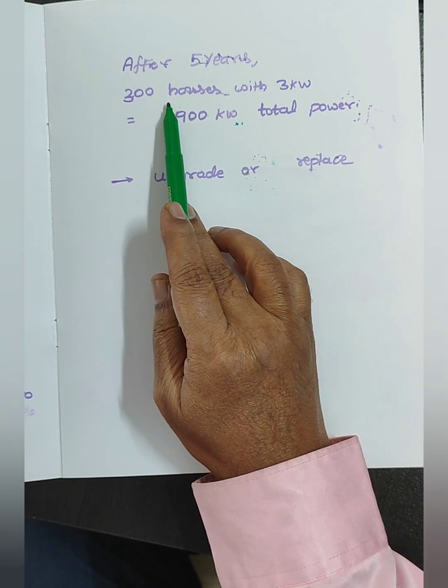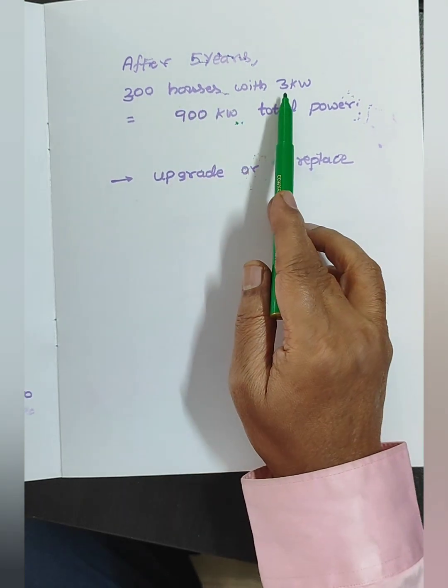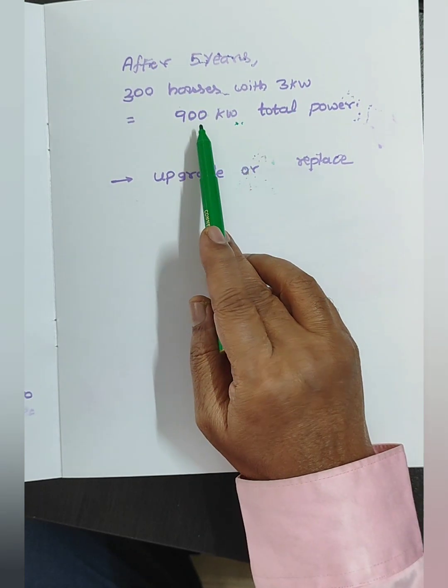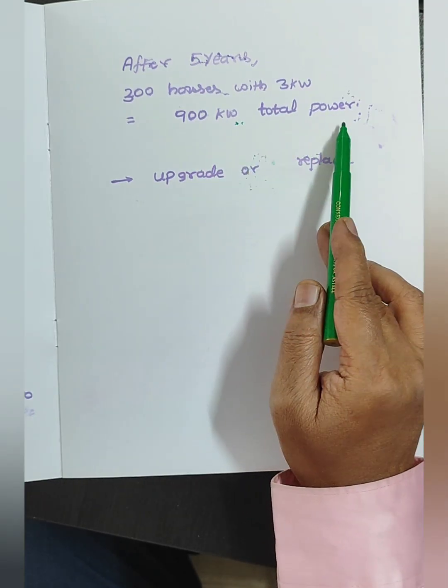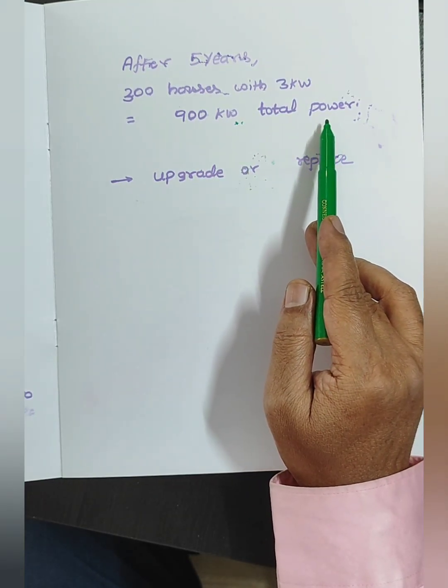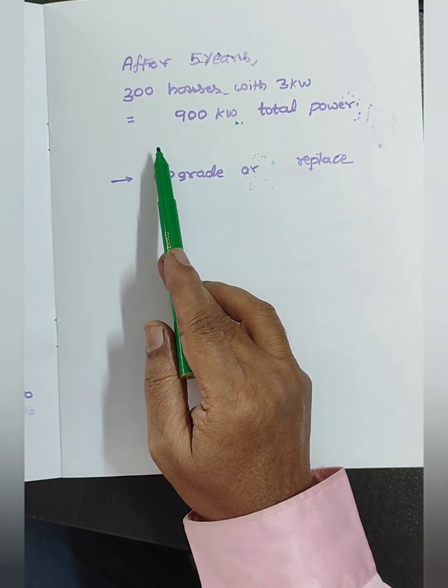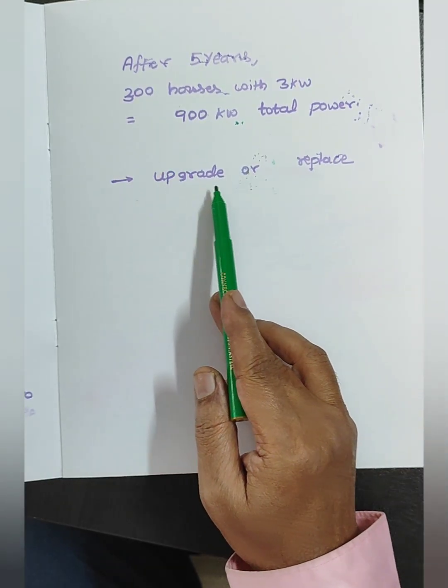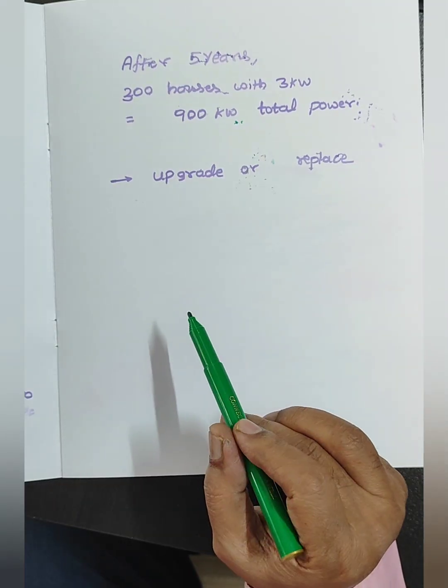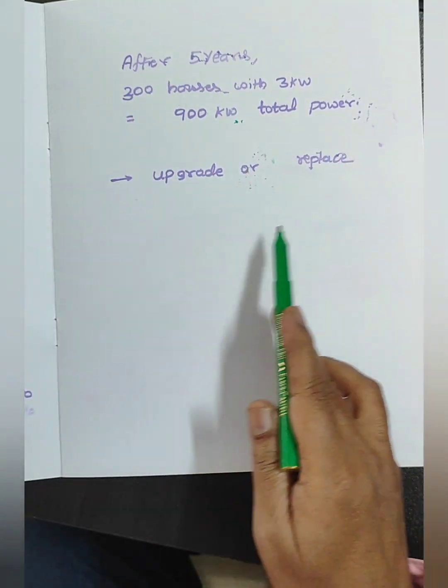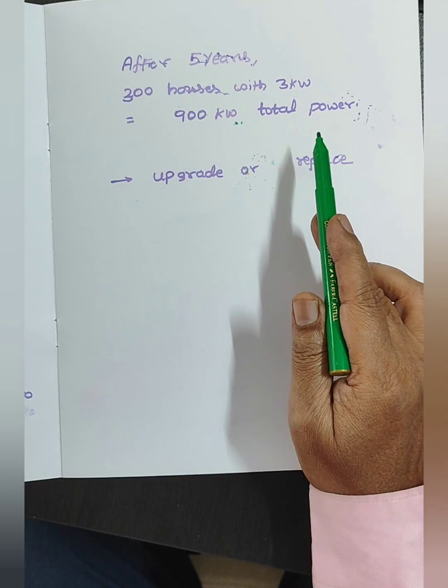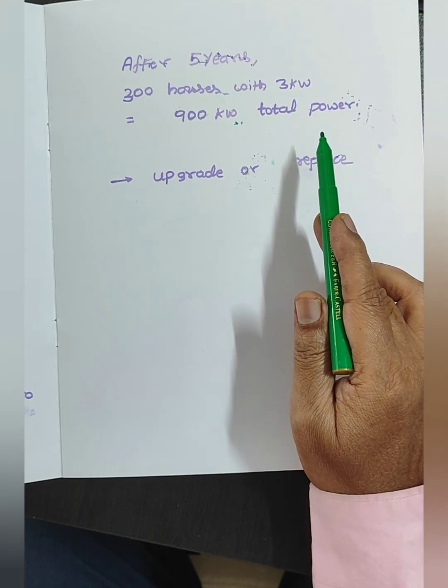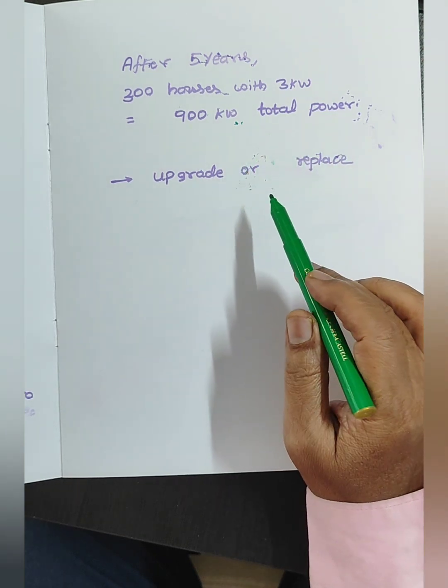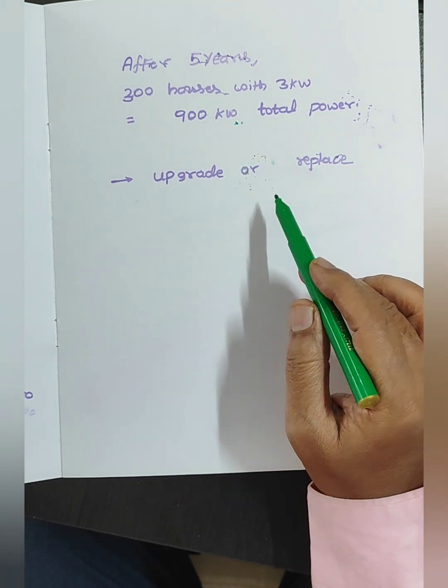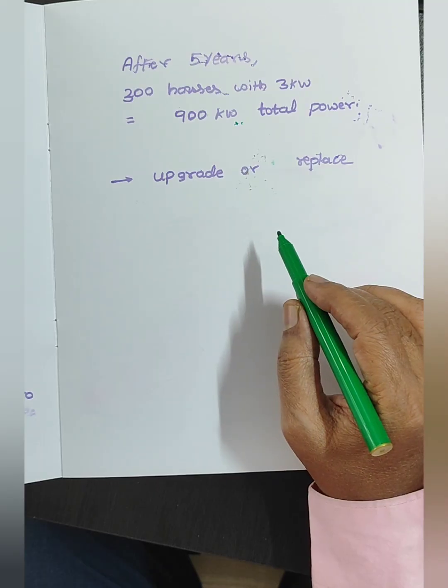There will be 300 houses instead of 100, with 3 kilowatts each. Now the total power is 900 kilowatts, but the capacity of the transformer is only 500 kilowatts, and we have to upgrade or replace it. This particular thing is to be done from the government side or BESCOM side, and I'll tell you the scenario of how it actually happens.